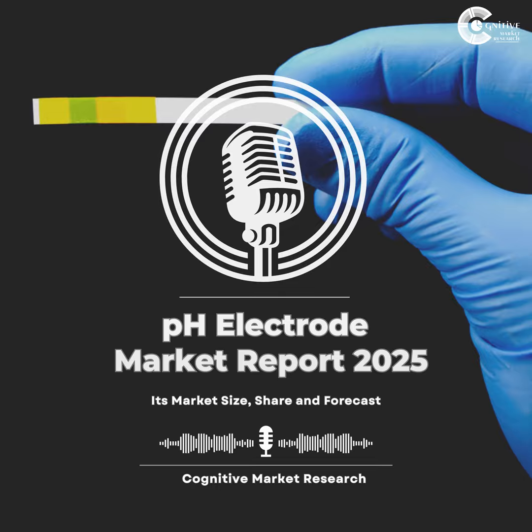Okay, so we have these powerful drivers, these undeniable benefits: water, pharma, industry. But I imagine there are significant hurdles too. It can't all be smooth sailing. What are some of the practical challenges? What keeps these electrodes from being completely set it and forget it? You've absolutely hit on a critical point there. It's definitely not set it and forget it. The first big challenge lies in their necessary calibration and maintenance. It's ongoing. pH electrodes require pretty frequent upkeep. Cleaning, proper storage, and calibration that's specific to the environment they're in, all needed to maintain accuracy. And without skilled personnel, without that diligent attention, improper handling can easily lead to sensor drift.